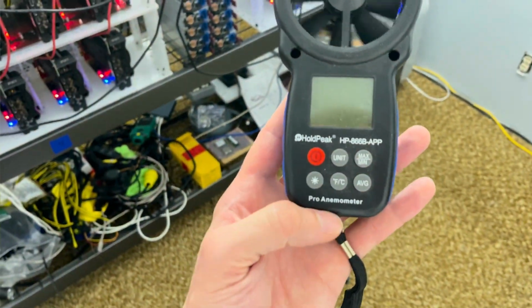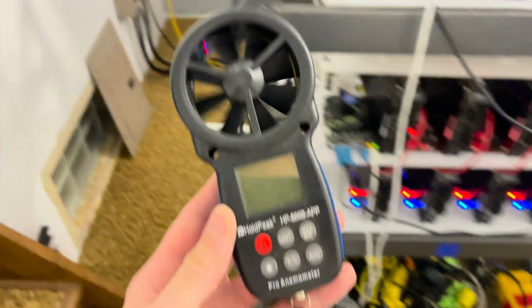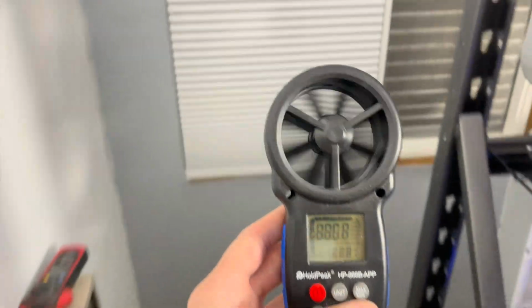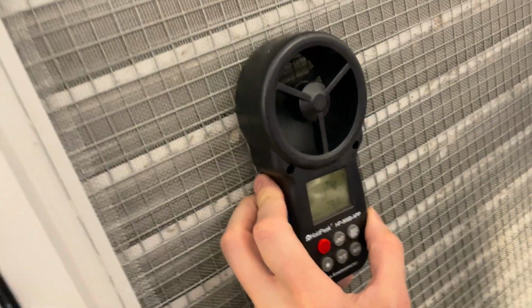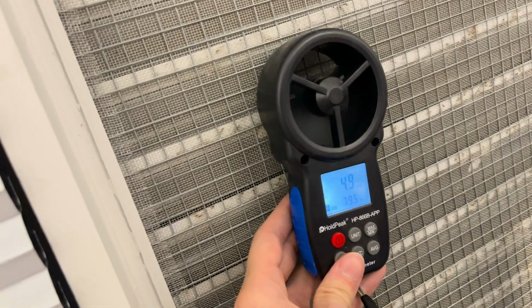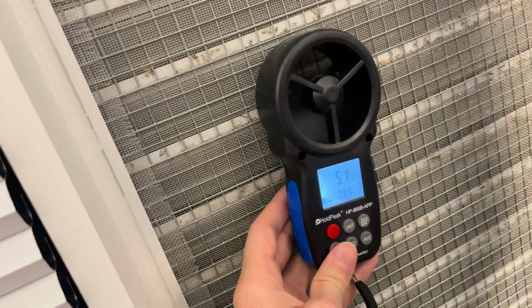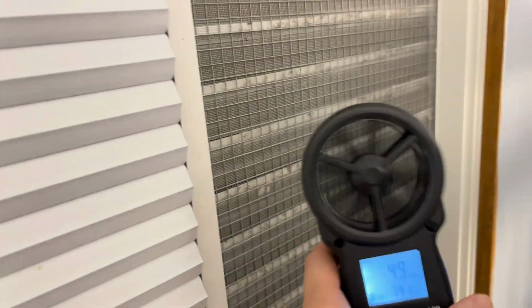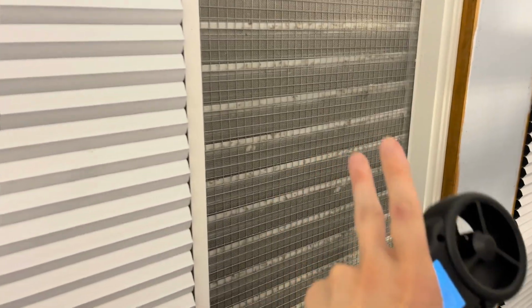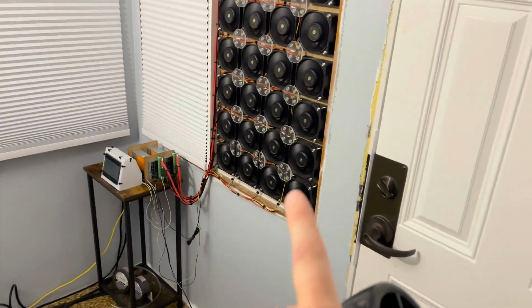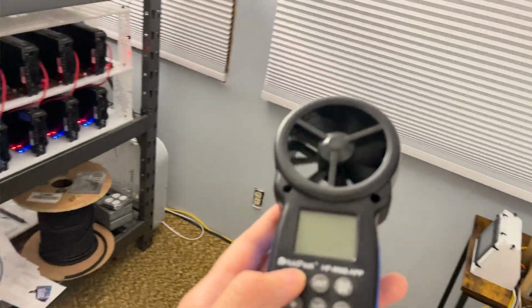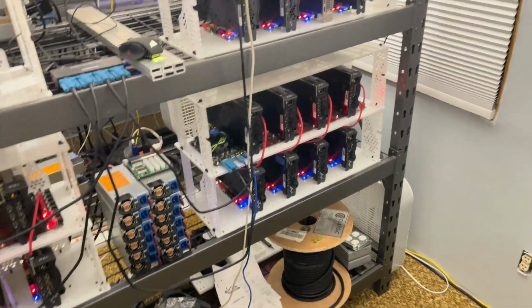Now, in place, you could use inexpensive tools like this guy to measure the airspeed. And using that, you can measure the airspeed through here. And if you check that it's relatively even throughout the area, you could plug it into calculators and figure out how much airflow you're getting through this volume. And you could estimate how much air this fan is pulling through the building. So you could use that as a benchmark to maybe further educate yourself or guesstimate how much you need. Just kind of set up as a benchmark or a baseline.